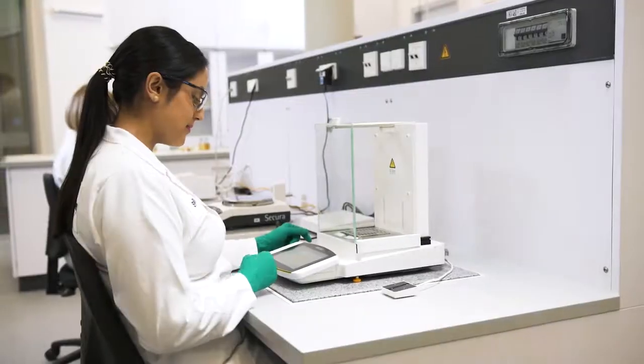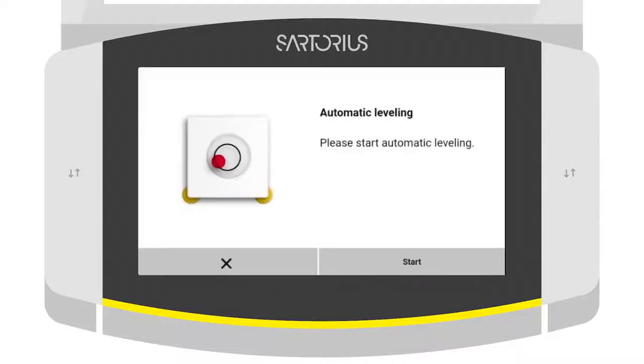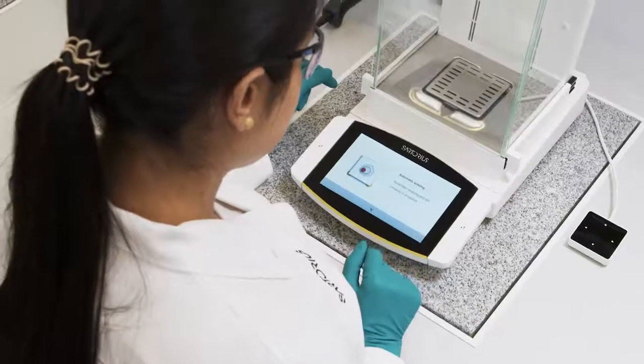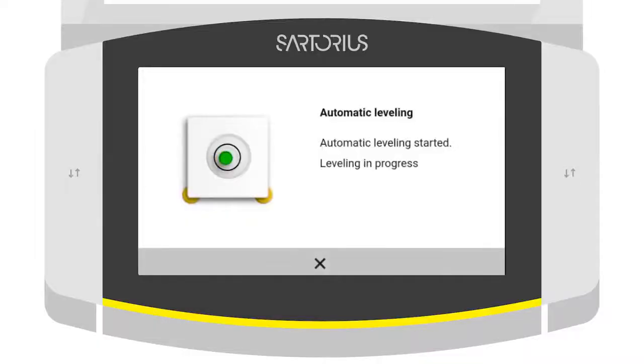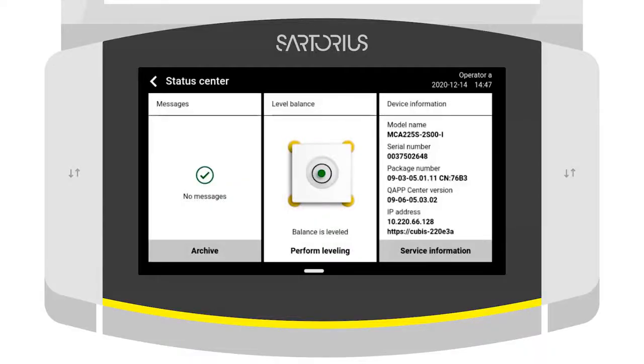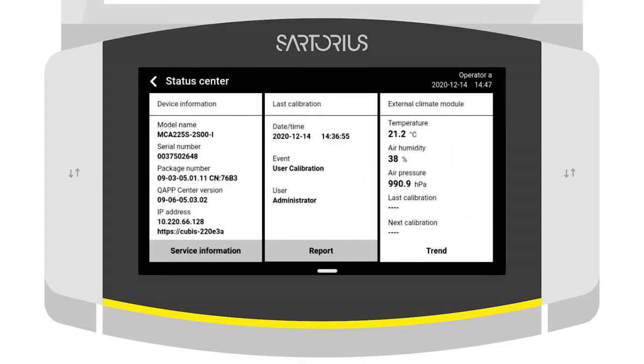Regular checks of your laboratory balances are essential to identify malfunctions at an early stage and to eliminate inaccuracies. Cubis II makes checking easier and prevents errors through intelligent functions and workflow support. The Balance Status Center is more than just a green light — it helps you get a comprehensive overview of all relevant status information and to solve problems.